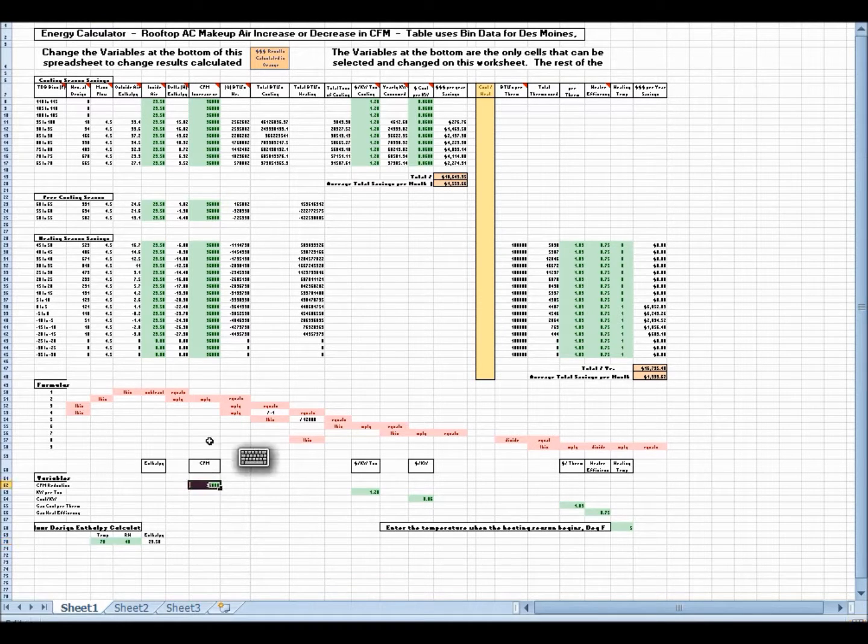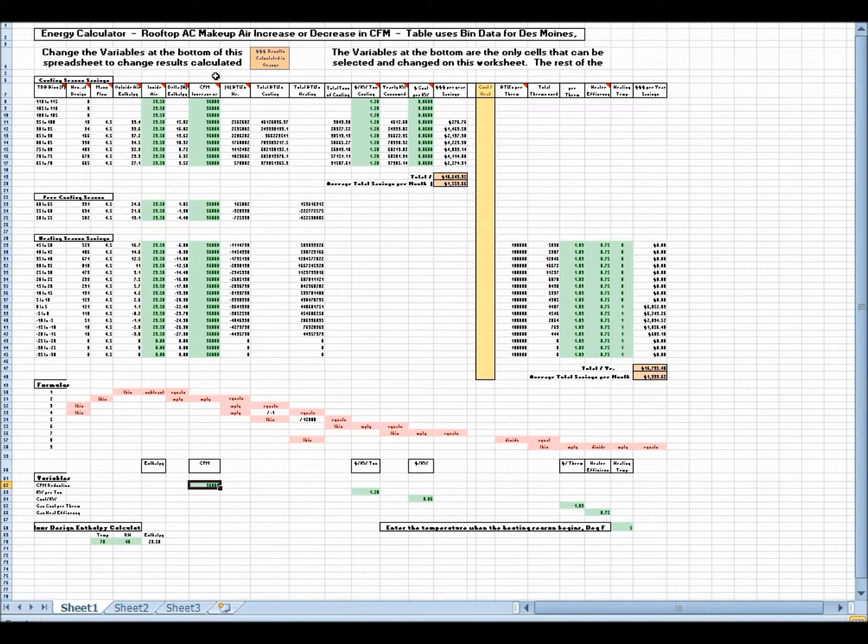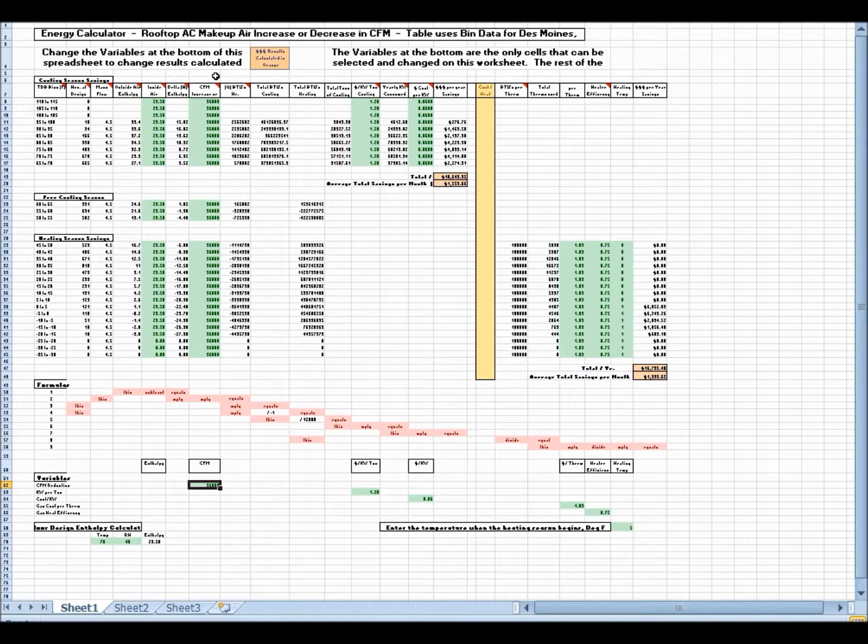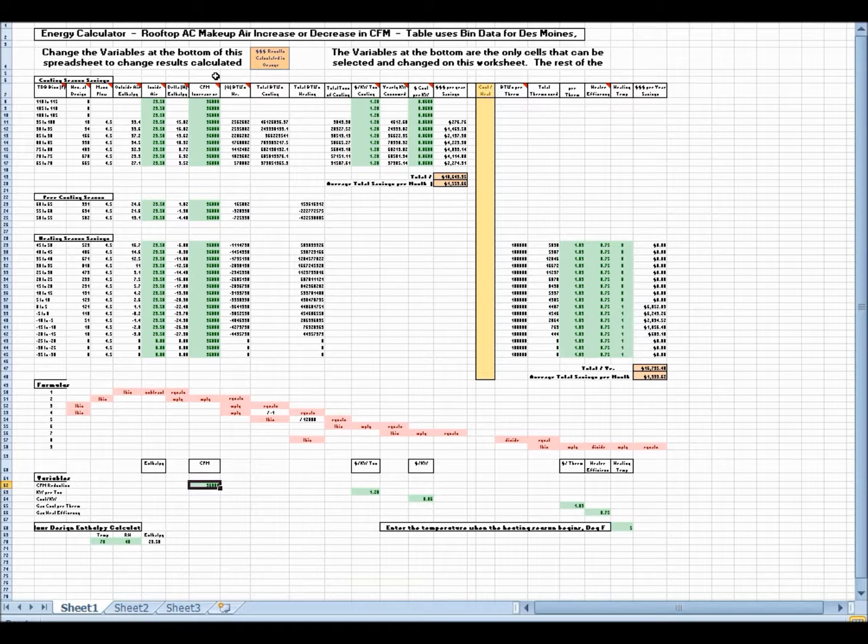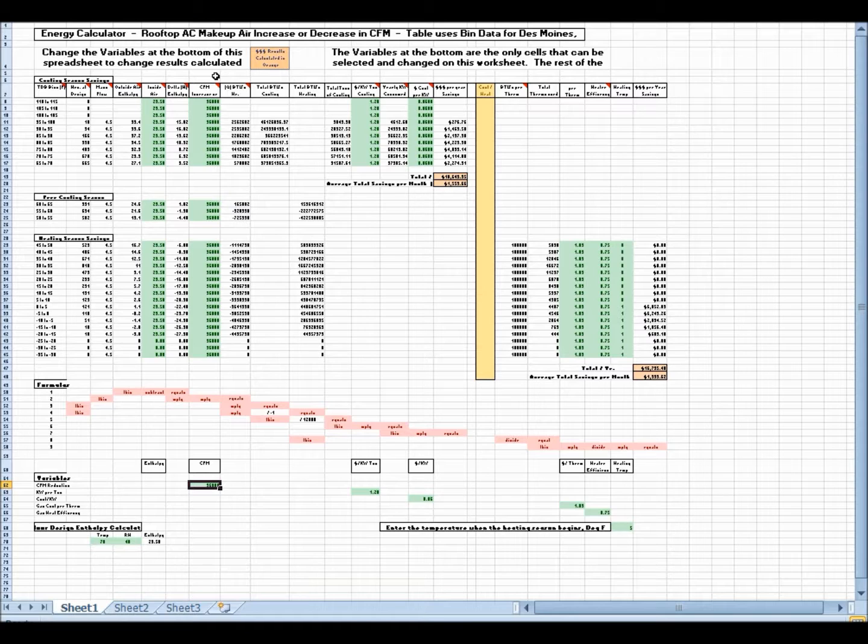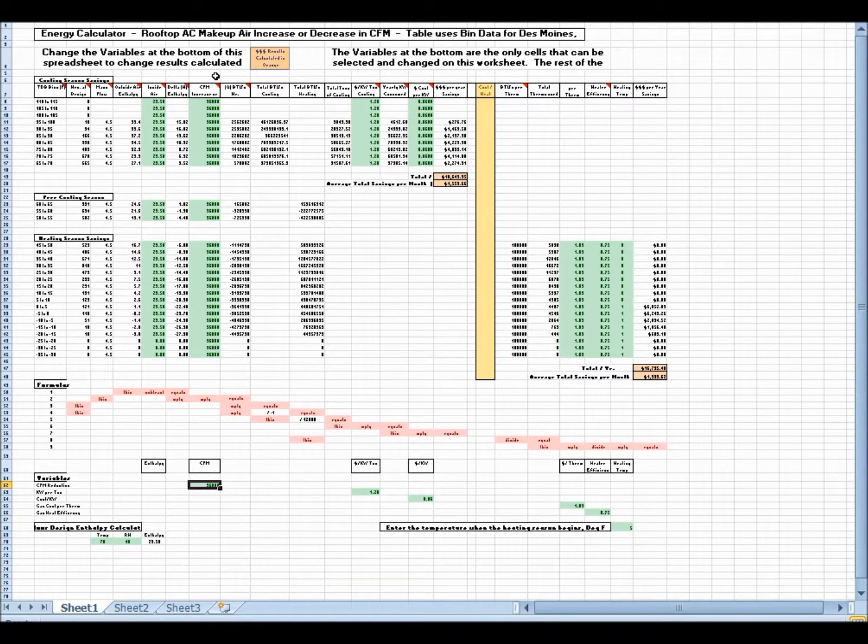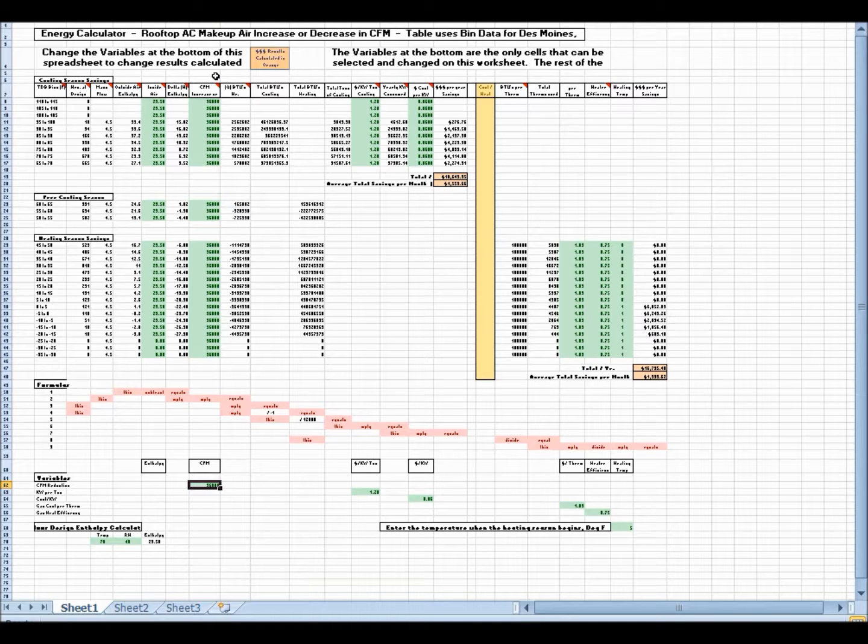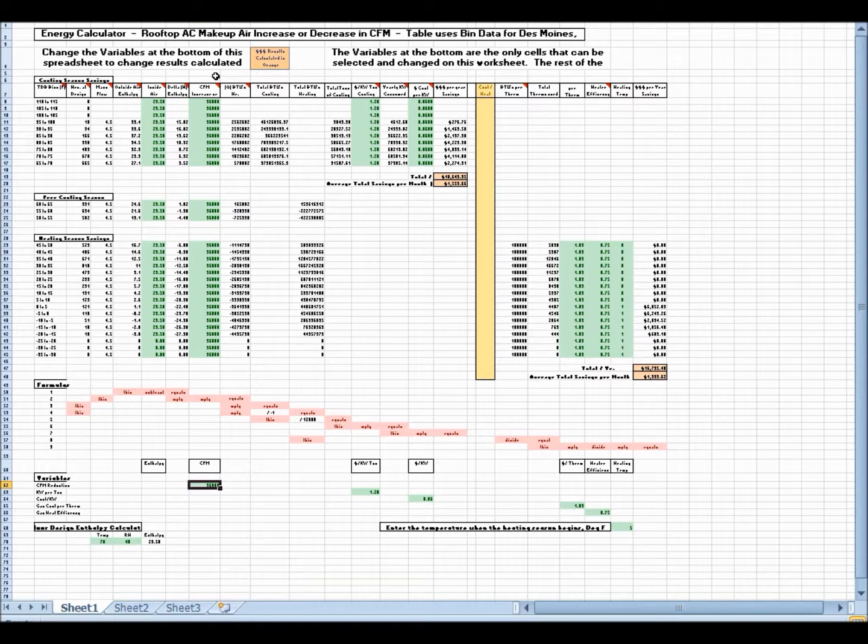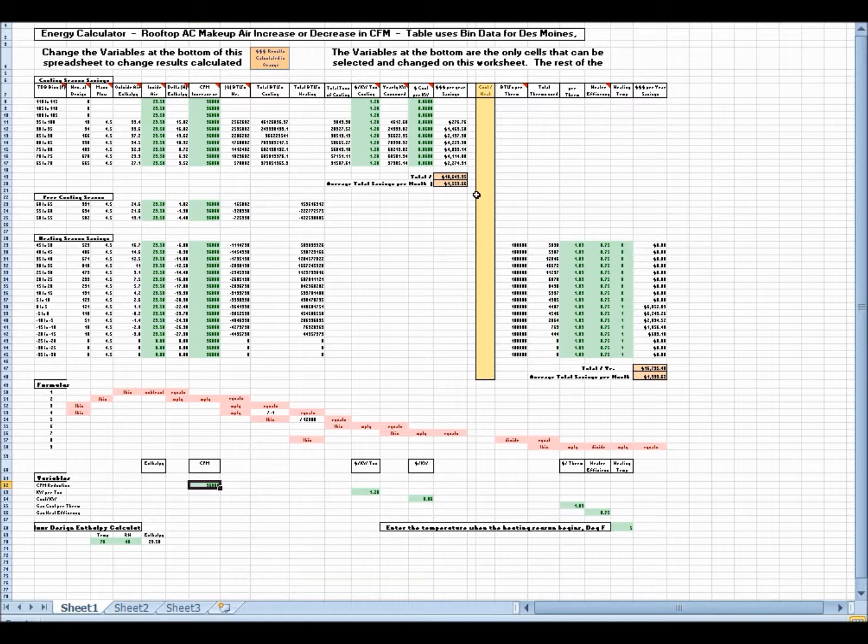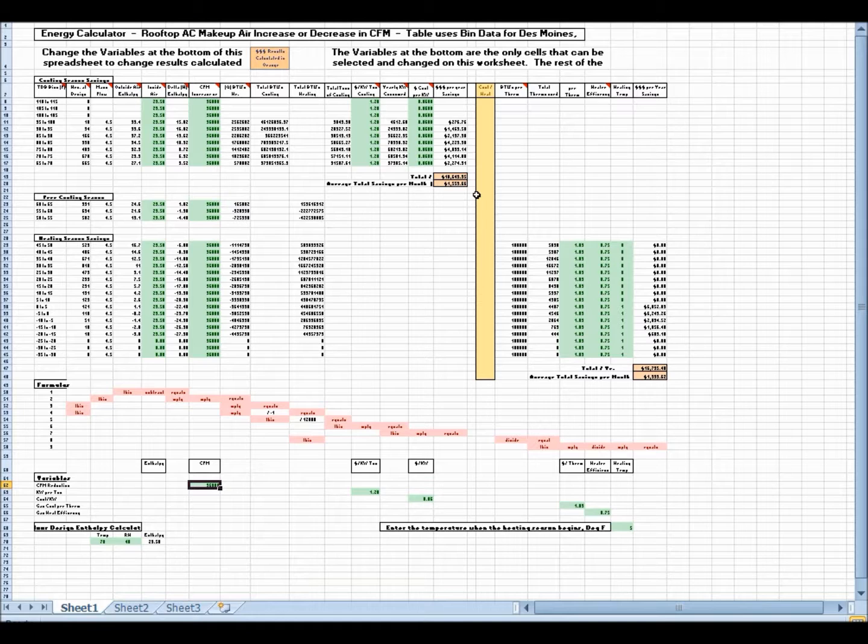Here, this is CFM. Right there of 24,000, oh, that one's 36,000 CFM. How do you know exactly what your fresh air coming to your building is? You can talk to your HVAC tech and say, yeah, we got 24,000 CFM. Cut it down to 12,000 CFM. That's a very difficult thing to do, to know that you're back down to 12,000 CFM. That can vary 15%, 20%. And then it's the actual linkage within the damper itself that is hard to keep accurate. That right there is just not a very accurate measurement. So, these values here, again, are just approximations to give you a good idea of what you might save if you cut down your CFM.